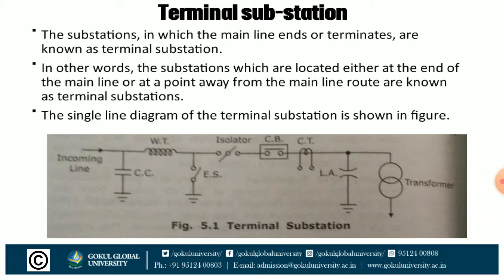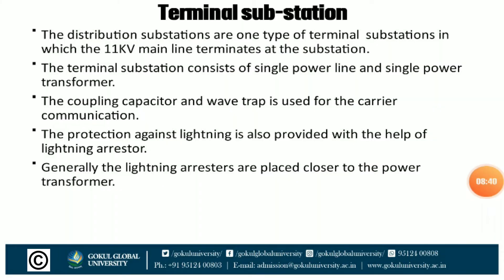The substation in which the main line ends or terminates is known as the terminal substation. In other words, substations located either at the end of the main line or at a point away from the main line route are known as terminal substations. The distribution substation is one type of terminal substation in which the 11 kV main line terminates at the substation. It consists of a single power line and single power transformer. Coupling capacitor and wave trap are used for carrier communications, and protection against lightning is provided with the help of lightning arrestors, generally applied closer to the power transformers.